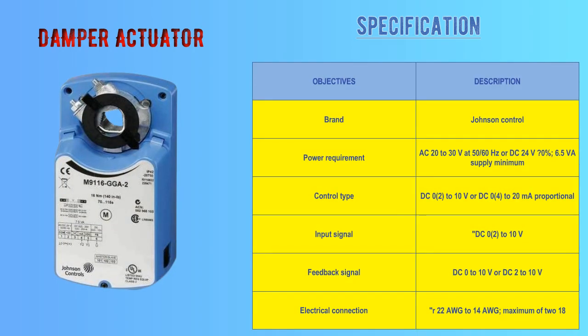Second, this is a product of Johnson Controls. This is called a Damper Actuator. It is used to control the damper such as fresh air, return air, mixed air, or supply air damper, depending upon the sequence. This is a modulating type damper, meaning it works between 0 to 100%. It takes 24 volt AC constant power, and for modulating, 0 to 10 VDC or 4 to 20 milliampere. This actuator gives feedback in DC volts.